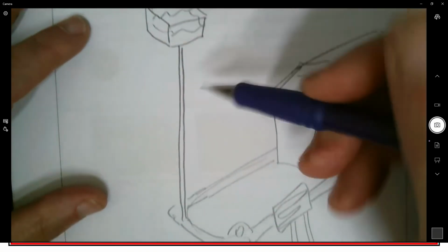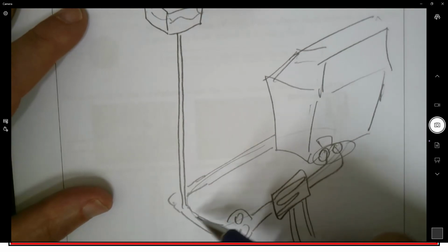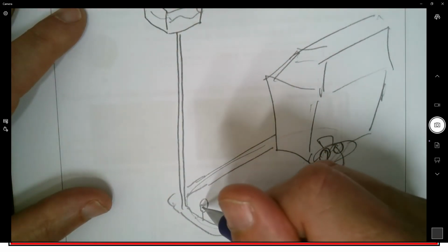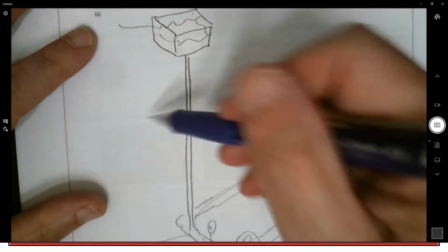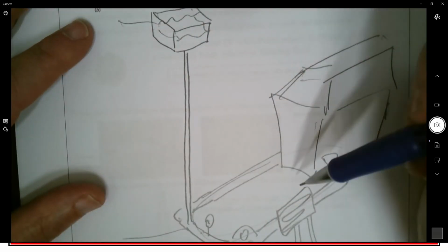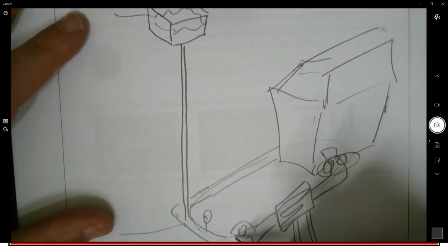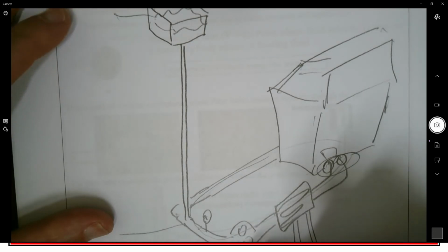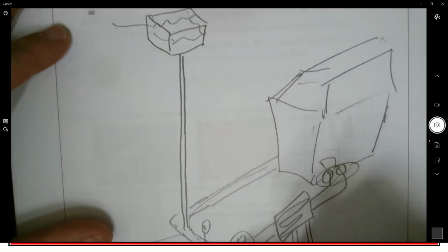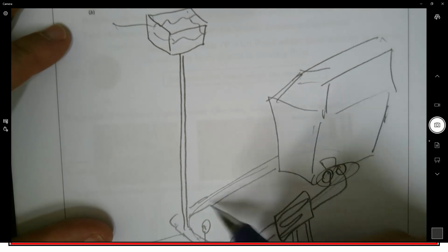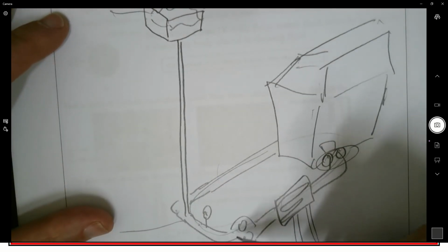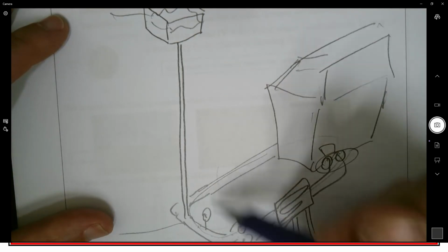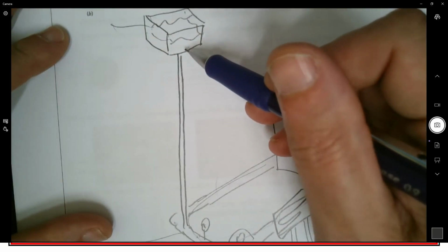But this tank serves to set what this pressure is going to be. That pressure has to be this elevation right here. This elevation is like a pressure regulating system, making sure that this pump, because it's hot water, right? One thing you don't want to do, and the heat exchanger might be on the other side, by the way. But hot water will make this pump cavitate. So we're going to keep a pressure in this system all the time by having this head tank.